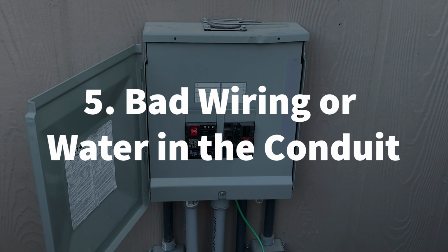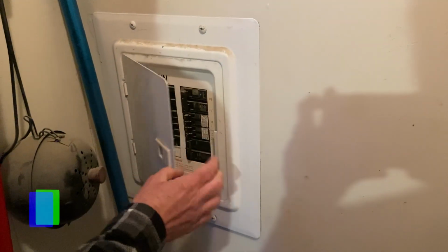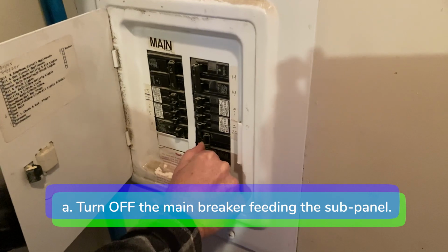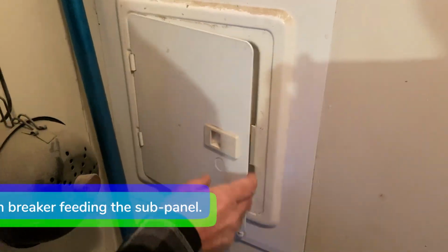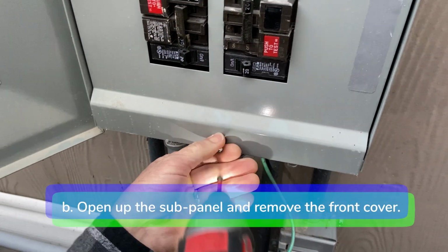5. Bad wiring or water in the conduit. If the wiring going from the sub-panel to the spa has been compromised, or if the conduit has filled with water, it will cause the breaker to trip. To troubleshoot, follow these steps. A. Go to the main electrical panel and turn off the breaker feeding the sub-panel. B. Open up the sub-panel and remove the front cover.